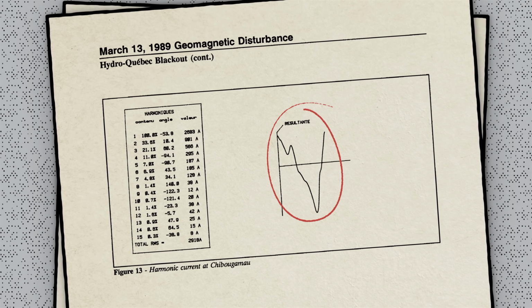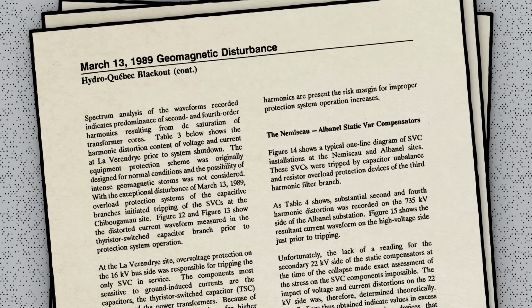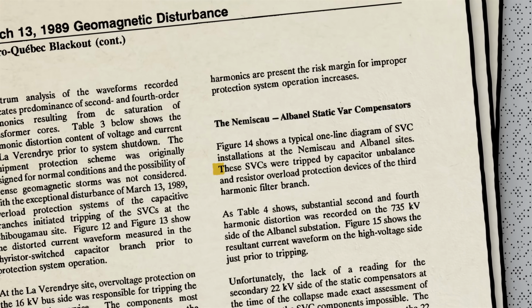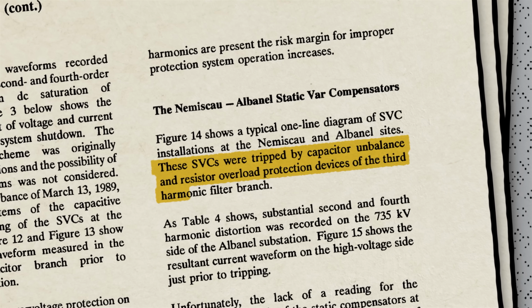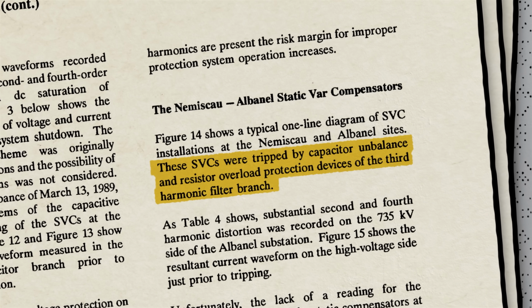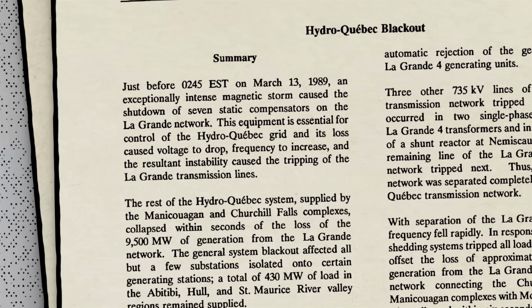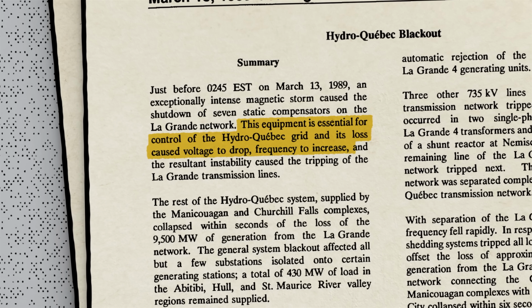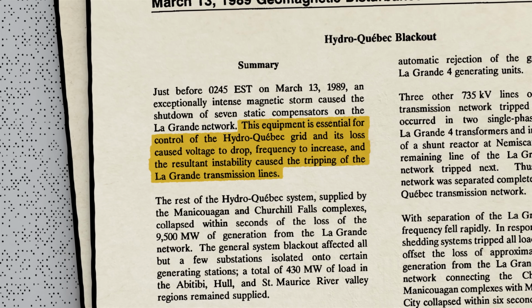The SVCs weren't configured to handle the dynamic conditions affecting the system, so relays designed to protect them tripped, pulling the equipment out of service. Without the SVCs, the voltage on the grid dropped, the frequency increased, and chaos ensued.